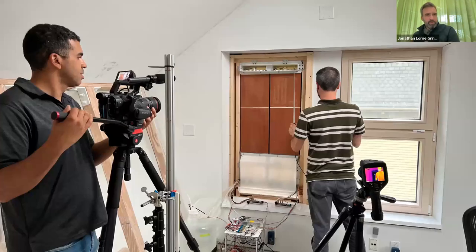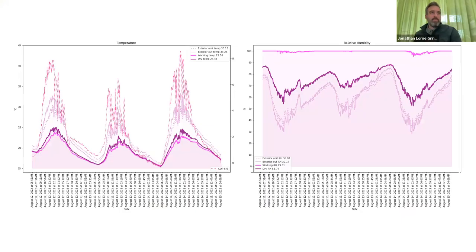And so over 2 weeks of time, we monitor different things like temperature and humidity and the overall performance of water use and electrical use of the system. And we start to map that out. So we won't get too deep into this, but on the left side is the temperature profiles over 3 days. Again, we took these 3-day chunks over a 2-week period, and the humidity. And so in this case, the takeaway is quite good.